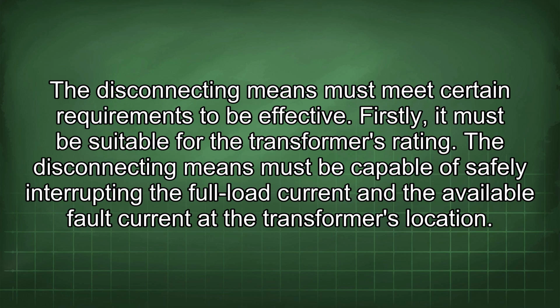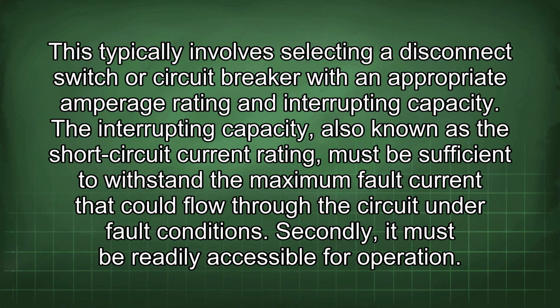The disconnecting means must meet certain requirements to be effective. Firstly, it must be suitable for the transformer's rating. The disconnecting means must be capable of safely interrupting the full load current and the available fault current at the transformer's location. This typically involves selecting a disconnect switch or circuit breaker with an appropriate amperage rating and interrupting capacity. The interrupting capacity, also known as the short circuit current rating, must be sufficient to withstand the maximum fault current that could flow through the circuit under fault conditions.